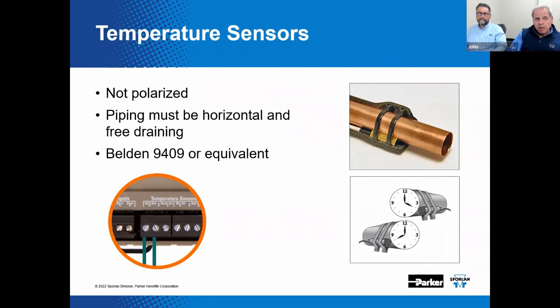Here's some detail on how to actually mount the bulb, if you will, of the temperature sensor. Again, they're not polarized. Piping must be on a horizontal free draining line, and that kind of sounds like we're mounting a bulb for a thermostatic expansion valve. We're kind of detailing the 4 and 8 o'clock positions on a refrigerant line. We also give you a more detailed view of how to do that.